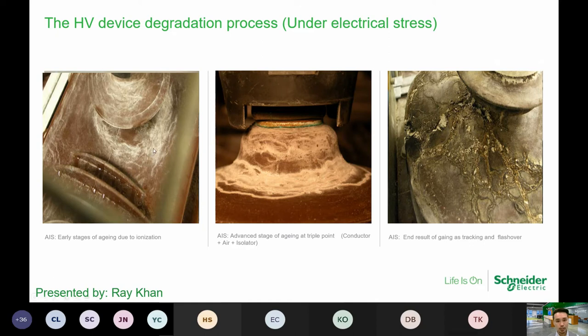So the picture shows an insulation material supporting the bus bar. The insulation is commonly at the top of the circuit breaker. The bus bar is mounted on the top of this insulation. So it has basically two functions. One function is to support the bus bar. Of course, the second function is to act as insulation. Now, since there's insulation, why does ionization occur? Reason why is because the current is trying to reach the metal structure on the panel itself. So that is why you can see the white stain in here.